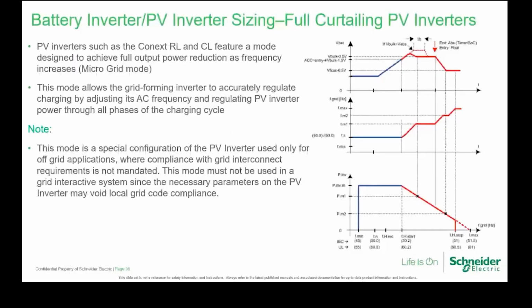So we look at the fully curtailing PV inverters, such as all the legacy RLs and CLs. Basically, what it can do is a thing called microgrid mode. This allows the grid-forming inverter to accurately regulate charging by adjusting its AC frequency and regulating the PV inverter power for all phases of the charging cycle. It makes sure that the batteries are fully charged and not overcharged. If you remember, you've got three-stage charging on the XW Plus and the XW Pro, where the first two phases are bulk and absorption. During the bulk stage, it is constant current, varying voltage. During the absorption stage, it is constant voltage, varying current. So if you want to vary that current, you've got to regulate the output of the PV inverter so that it doesn't overcharge the battery bank.